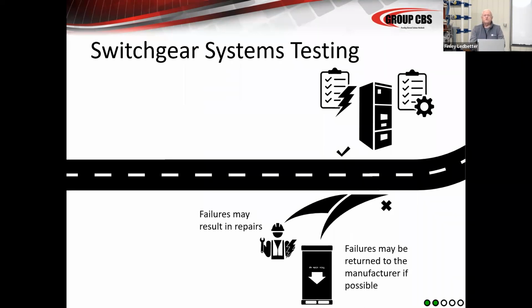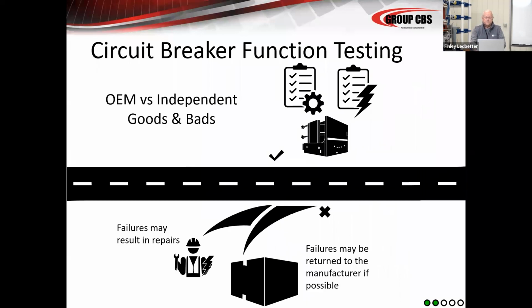Some of this stuff will be returned to the manufacturer, or the manufacturer will be contacted and told, hey, we've got a problem, and they'll send their factory service people out. Quite often, that's a third party that's calling out those deficiencies. So as the owner or as the contractor, you have to get in between that and referee that. That can be a little tough at times. But there is a path by which, if this does not pass acceptance testing, there is some give and take there. So you have to determine, do you use an OEM? Do you use an independent? What are the good and bads of both? And we'll discuss that in the next segment in great detail.